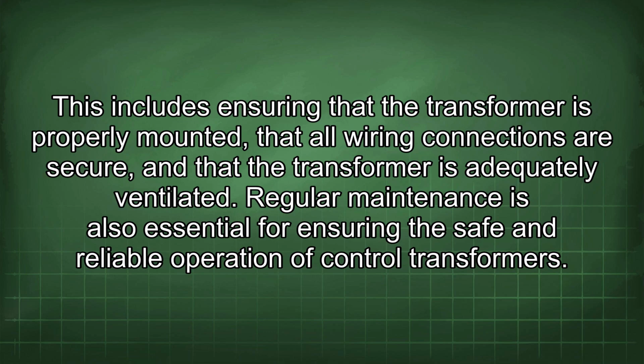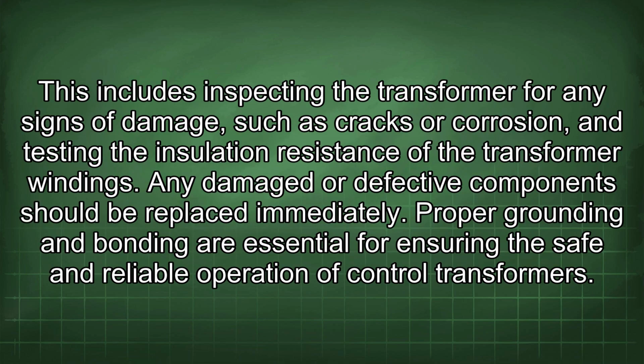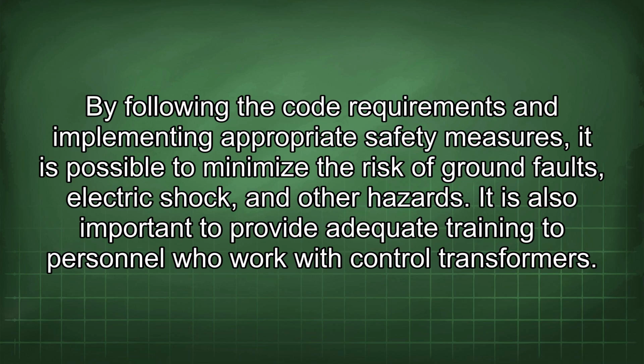adequately ventilated. Regular maintenance is also essential for ensuring the safe and reliable operation of control transformers. This includes inspecting the transformer for any signs of damage, such as cracks or corrosion, and testing the insulation resistance of the transformer windings. Any damaged or defective components should be replaced immediately. Proper grounding and bonding are essential for ensuring the safe and reliable operation of control transformers. By following the code requirements and implementing appropriate safety measures, it is possible to minimize the risk of ground faults, electric shock, and other hazards.